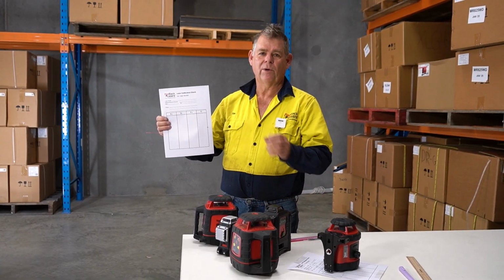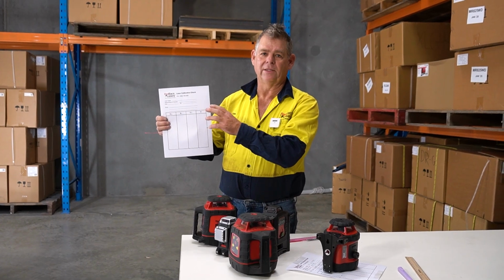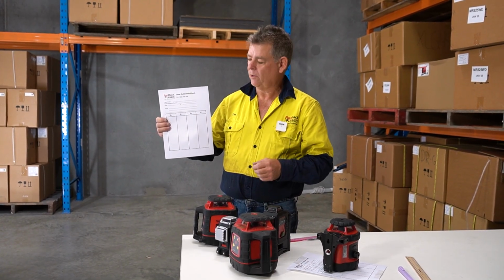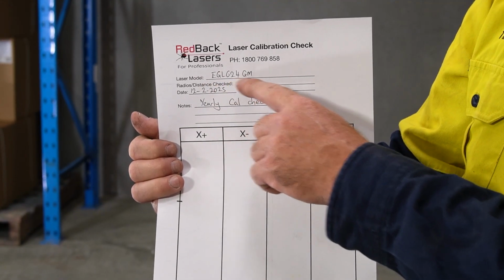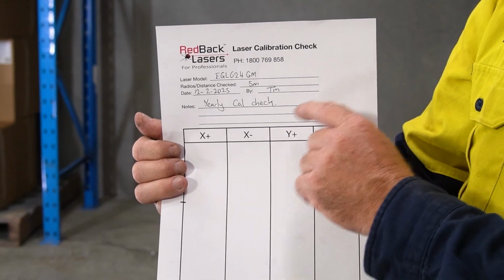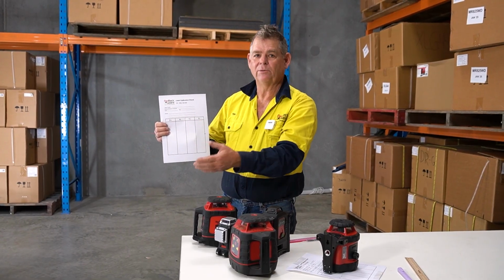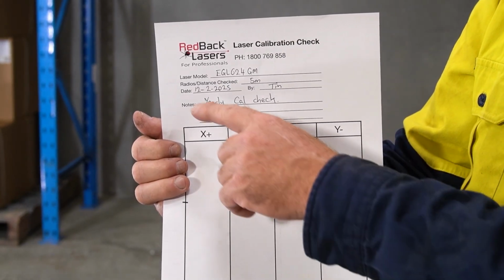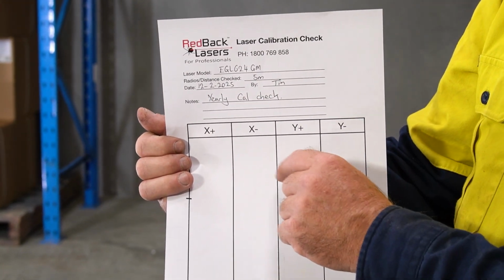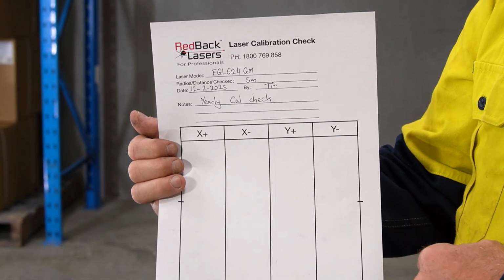So to start with, we're going to want to download a copy of that laser check sheet, which we can click on the link online. We've got the laser model there, and we can put our serial number down next to that. The distance or radius, which we want at least 5 meters. The date, who by, and a little note there, a yearly calibration check for us.